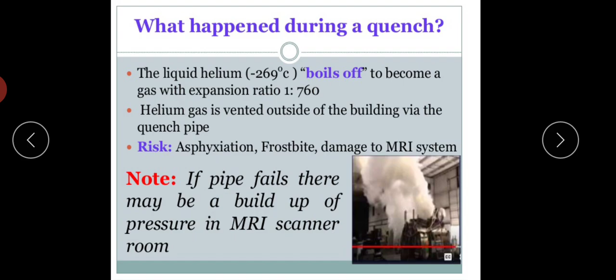So, during a quench, the liquid helium, which is initially at minus 269 degrees Celsius, boils off to become a gas with an expansion ratio of 1:760. Helium gas is vented outside of the building via the quench pipe. Risks: there can be frostbite, damage to the MRI system, and asphyxiation. Note, if the pipe fails, there may be a build up of pressure in the MRI scanner room.